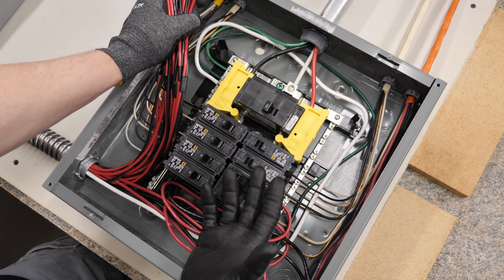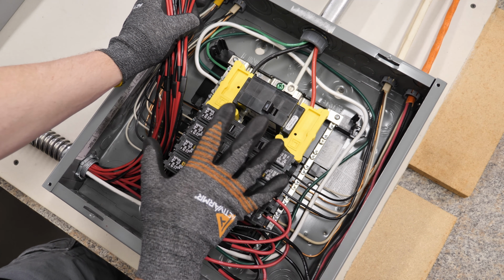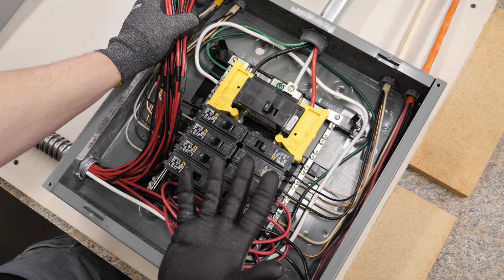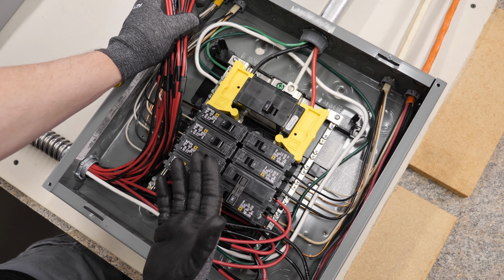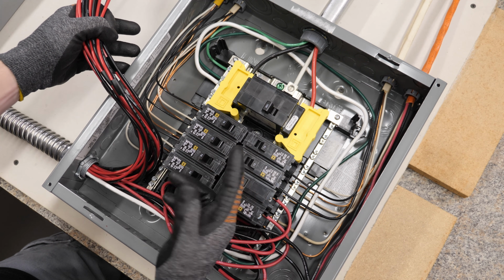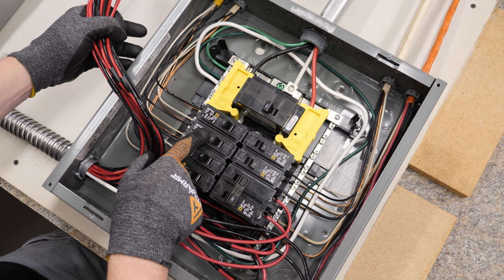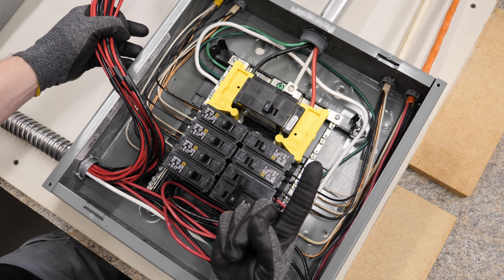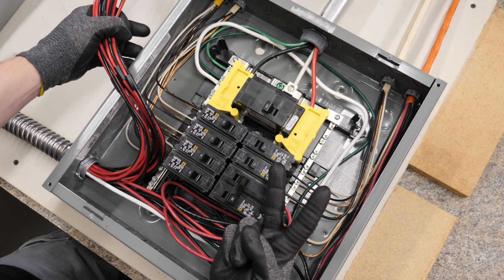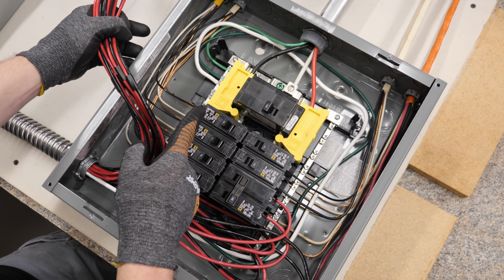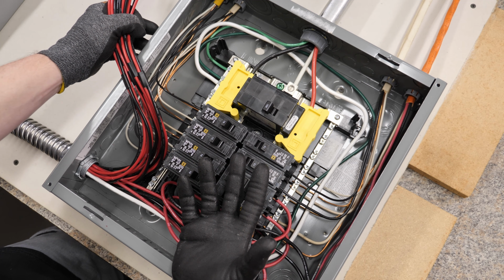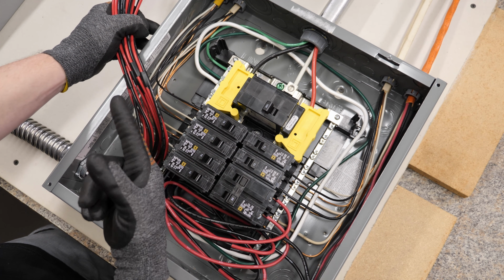The next thing you'd do, since you'll have more circuits than I do in this panel, is find the circuits you want to put on the critical loads panel. For this example, I'm only doing these two circuits right here - we'll say it's my refrigerator and my furnace. Since this is spot 1 and 3, I'm going to put those on circuits E and F in the critical loads panel.